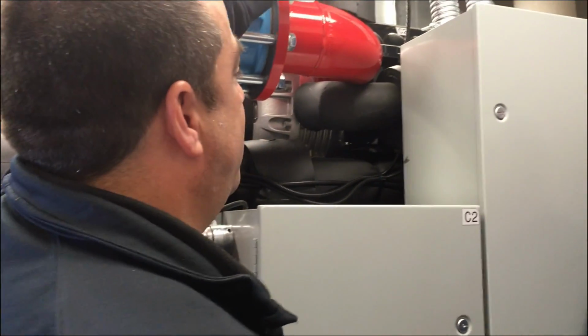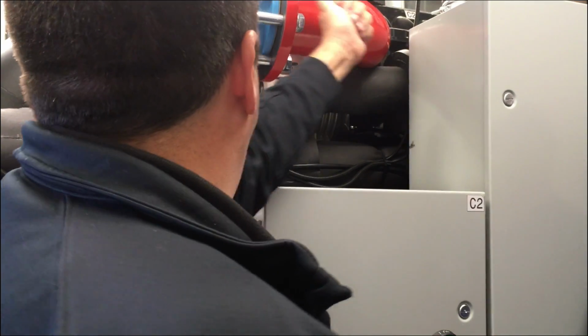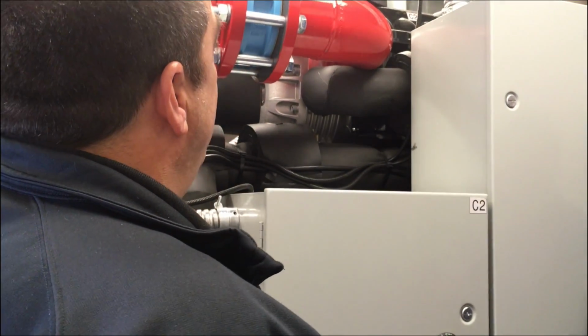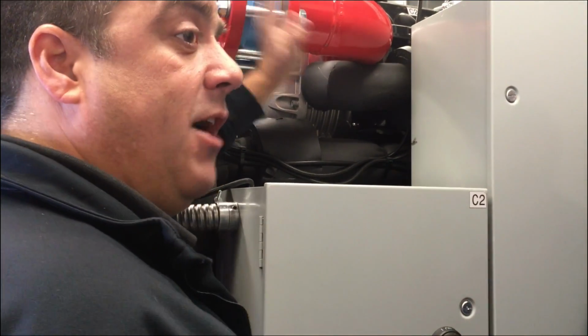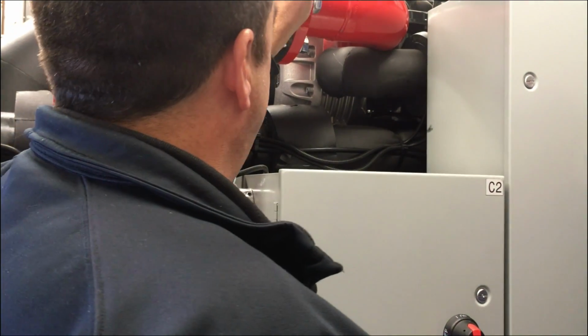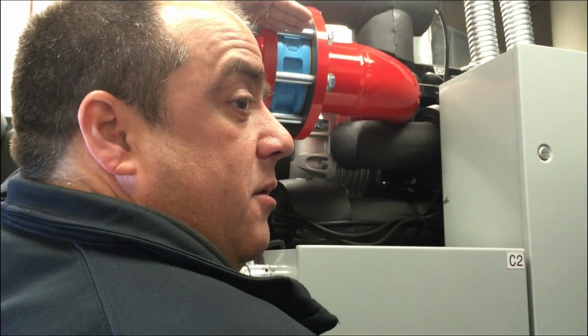About 60 seconds in, this valve will start to close. As it closes, it pushes refrigerant this way into the system, and you'll hear this check valve give a couple, 2, 3, 4, 5 bangs, and then it's gone. By that time the metal check is completely up this way, and it will sit there until this machine has pressure equalizing on both sides.